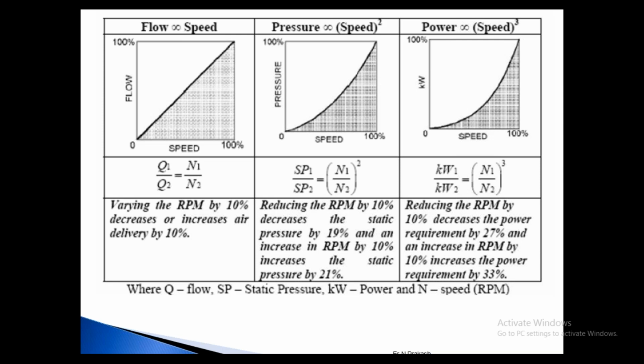Your humidification plant is designed for peak summer. It is not peak summer now, so you want to reduce slightly. When you are reducing the flow, automatically your pressure is also going to reduce. Power, of course, you are going to get the benefit. But when the pressure reduces, you have to see whether the airflow crosses the duct, the full length of the department, and overcomes the resistance.